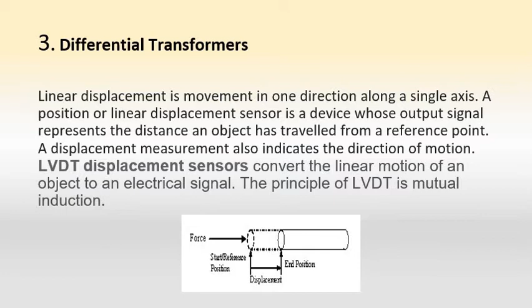These LVDTs operate on the principle of a transformer, that is, mutual induction. As shown in the figure on the right, the LVDT consists of a coil assembly and a core. The cylinder-type material shown in the center is the core, and around it three different coils are wound. From the right side, both end coils, the first and the third, are the secondary coils, and the center coil is the primary coil.